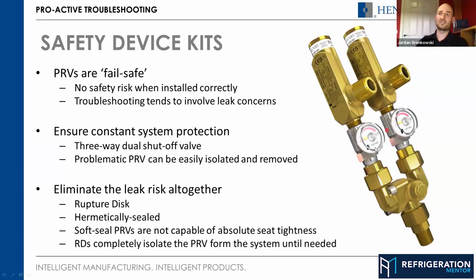Yeah. Well, I should have mentioned, obviously, you can see them here, and you indicated it there, Trevor, the rupture discs in our safety device kits come with these indicator gauges. It's difficult to see on the screen, but there's a little yellow arrow that will ping up when it sees pressure. It doesn't tell you how much the pressure is, but you can see visually straight away which valve has gone, without looking at the three-way valve to see which side is line, because the indicator gauge will be up saying there is pressure on this line. So it's an easy way to show which one's going. Yeah, no, that's awesome. I love this. I learned so much already.